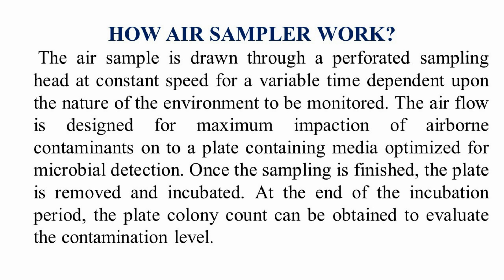In simple language, the sampler has a porous mesh. Behind that, the agar plate is placed, and just behind that plate a fan is placed. The fan sucks air through the porous mesh in a uniform direction. The air comes in contact with the agar plate and is eliminated from the backside of the sampler. After completion of sampling, the plates are incubated and observed for growth.